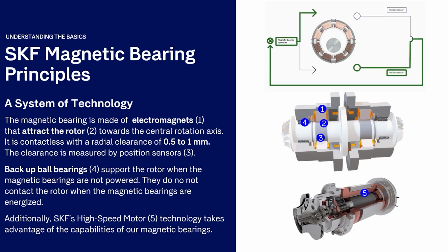The animation in the upper right corner shows how the different elements interact to control rotor position. When the rotor moves away from center, say pulled down by gravity, the position sensors register that change and send the detail to the magnetic bearing controller. This controller receives data from the sensor at about 20,000 signals per second, so it knows very well what's happening to the position of the rotor. With that information, it determines how much power to apply to the electromagnets, and as that power is applied, it pulls the rotor back into position. They repeat this process over and over, controlling the orbit of the rotor as the machine operates.